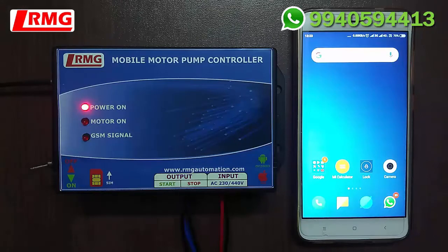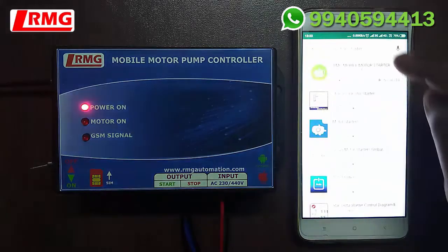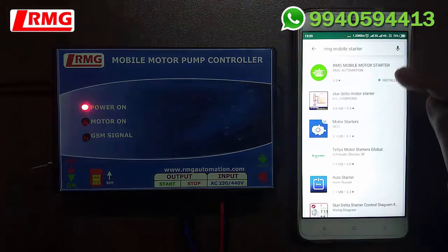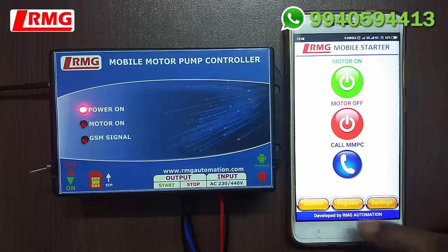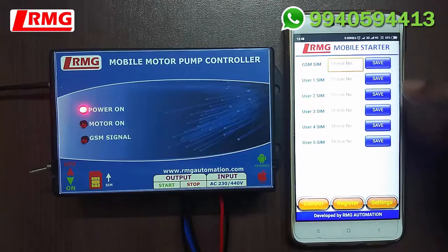Now let's see how to configure, control, and monitor the GSM unit. Go to the Play Store, search for 'RMG Mobile Starter' and install it on your Android phone. Open up the app and you can see three menus: Control menu, Register menu, and Settings menu. Click on the Register menu and enter your own GSM SIM number.